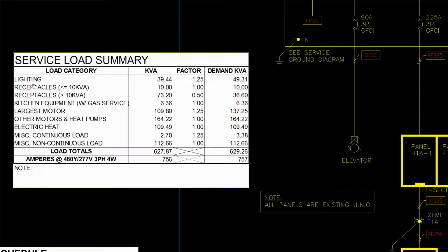And so we'll look at this and make sure that the factors are correct. The lighting is considered continuous, and there's a 1.25 factor, so 25% added for lighting. There are other miscellaneous continuous loads, and anything that stays on for 3 hours or more is considered continuous. Different heaters are required by code to be considered continuous, and so we get that. And we have miscellaneous non-continuous loads, so you see a lot of 1.0s.